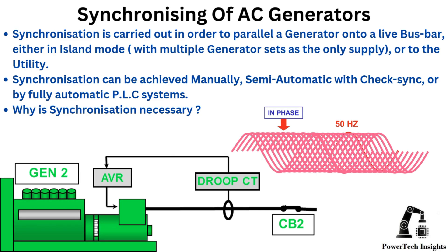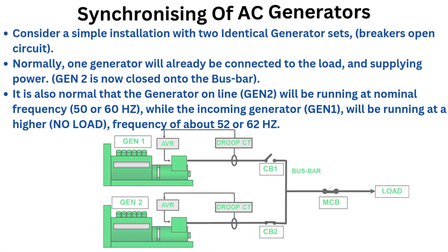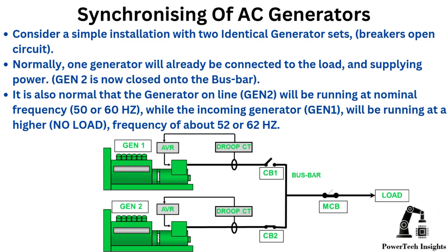Why is synchronization necessary? Consider a simple installation with two identical generator sets with breakers open circuit. Normally, one generator will already be connected to the load and supplying power. Gen 2 is now closed on the bus bar. It is also normal that the generator online, Gen 2, will be running at nominal frequency 50 or 60Hz, while the incoming generator Gen 1 will be running at a higher no-load frequency of about 52 or 62Hz.